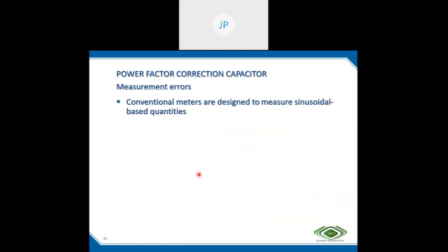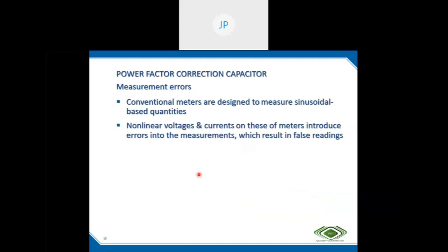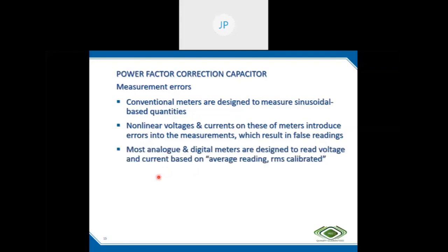Conventional meters are designed to measure only sinusoidal quantities. If we measure nonlinear voltages and currents with conventional meters, it will introduce errors and result in false readings. Most analog and digital meters are designed on average reading, RMS calibrated. Actually, we know the RMS by average ratio, the form factor, is 1.11. So if we measure the average value and multiply it, we can calibrate and display it as the RMS value. This is what our old conventional meters are doing. Actually, it is not the true value.